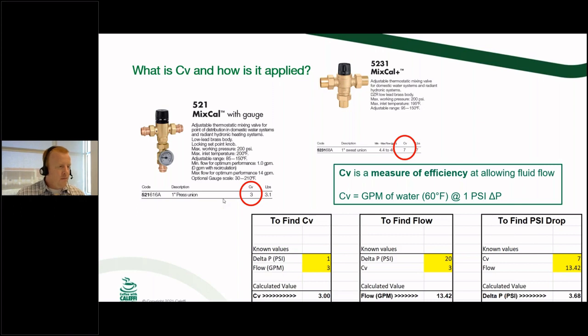Just don't shoot from the hip and say I need a 2-inch mixing valve, because maybe this building has been repurposed for whatever reason, and maybe they used a lot of water before, but now they don't use a lot of water anymore, and now all of a sudden you've got this giant mixing valve in there for an occupant in this building that doesn't need all that water and doesn't need that big huge mixing valve. So again, just be really careful with that.